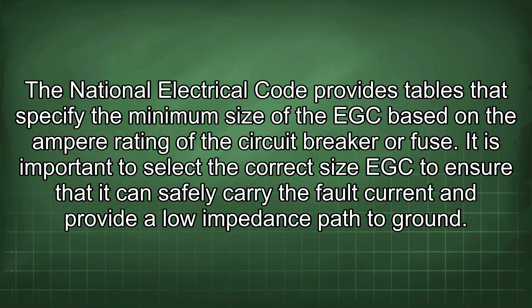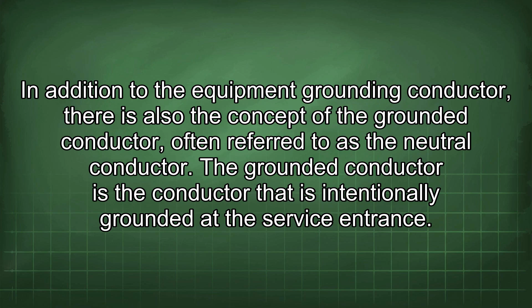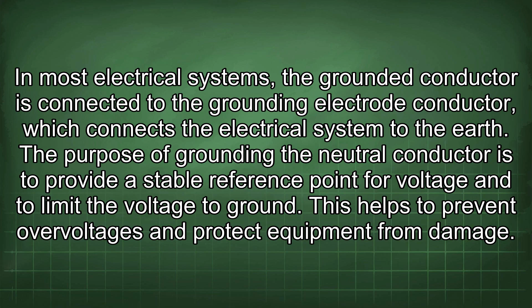In addition to the equipment grounding conductor, there is also the concept of the grounded conductor, often referred to as the neutral conductor. The grounded conductor is the conductor that is intentionally grounded at the service entrance. In most electrical systems, the grounded conductor is connected to the grounding electrode conductor, which connects the electrical system to the earth. The purpose of grounding the neutral conductor is to provide a stable reference point for voltage and to limit the voltage to ground. This helps to prevent overvoltages and protect equipment from damage.